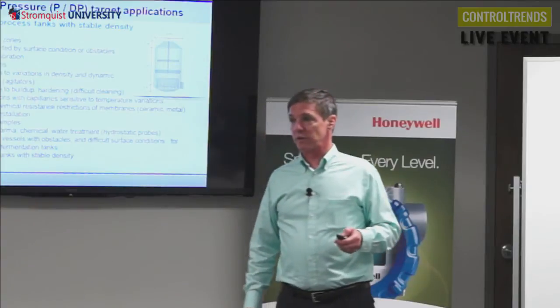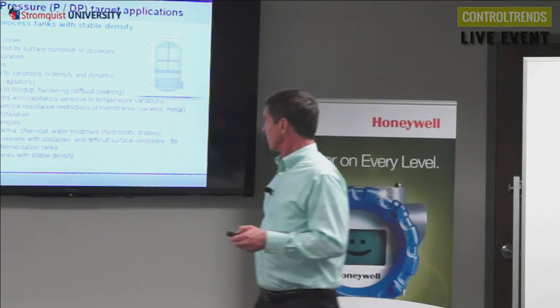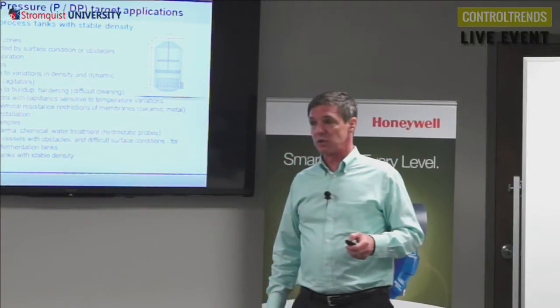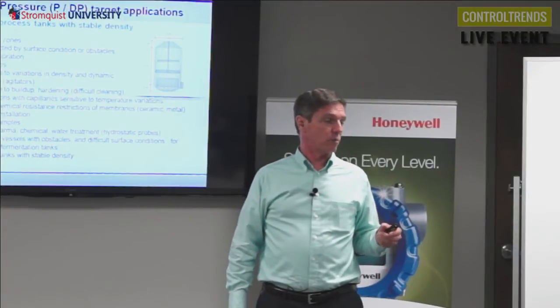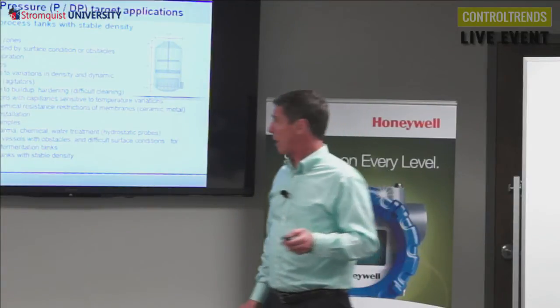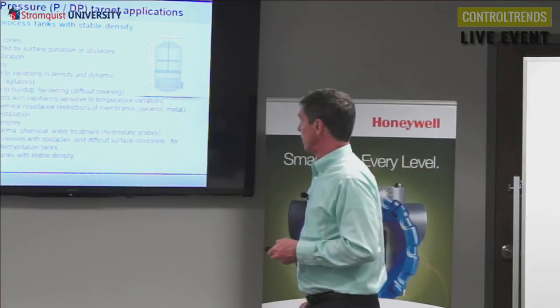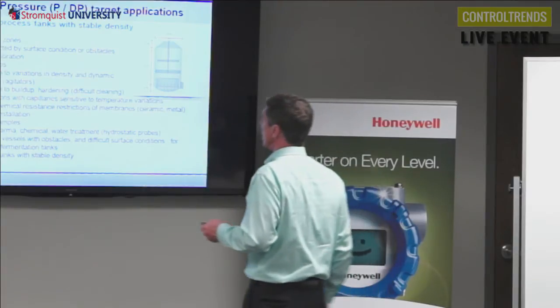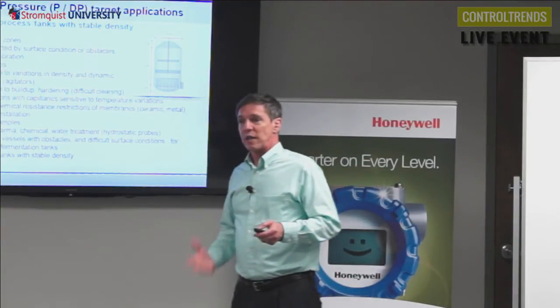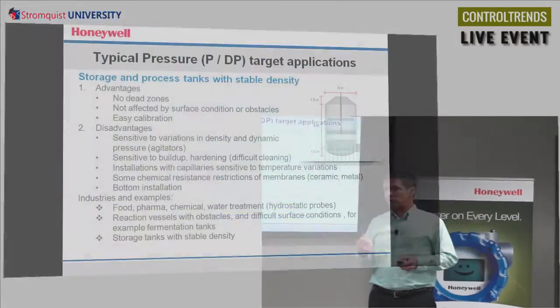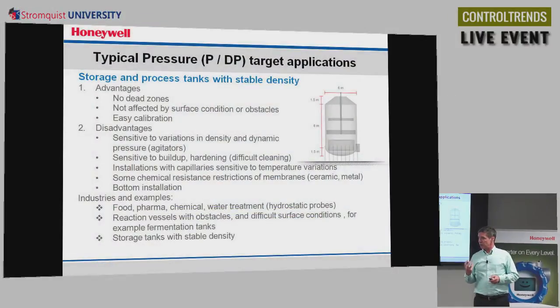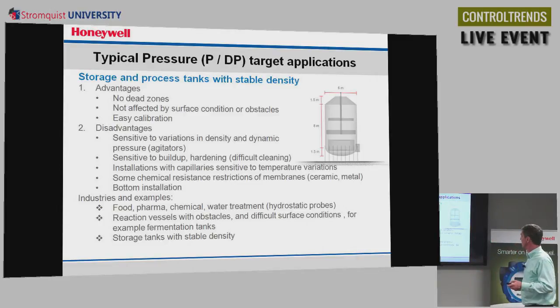So the advantages of this are there's no dead zones. It's not affected by turbulence or any kind of surface conditions. Foam doesn't matter. We don't have those things to worry about. And it's fairly easy to calibrate. The big disadvantage is that it's sensitive to changes in density. So you really need to have a constant density for this to work, because you're assuming that density is a certain value and it's going to stay that way.